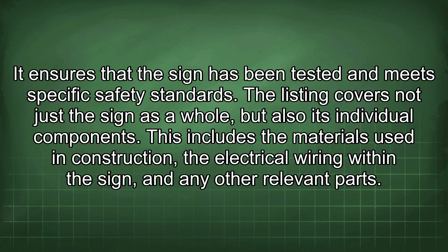Electrical signs are governed by Article 600.3 of the National Electrical Code. This section is very clear, stating that electrical signs must be listed and labeled by a nationally recognized testing laboratory. This is an important requirement. It ensures that the sign has been tested and meets specific safety standards. The listing covers not just the sign as a whole, but also its individual components, including the materials used in construction, the electrical wiring within the sign, and any other relevant parts. The purpose of this listing is to ensure that the sign is safe to install and operate. It helps to prevent electrical shocks, fires, and other hazards that can arise from faulty electrical equipment.